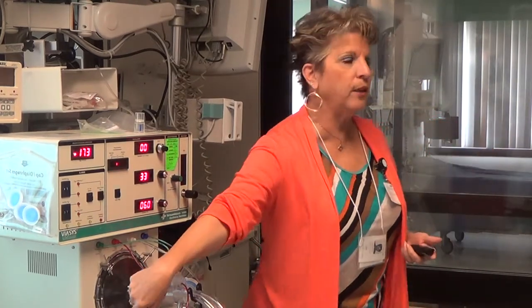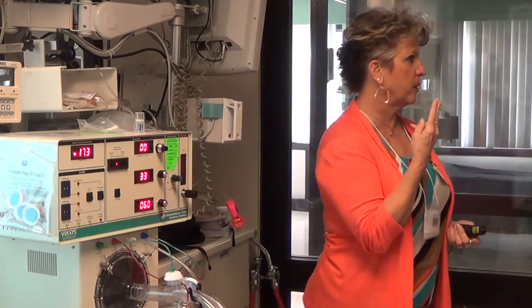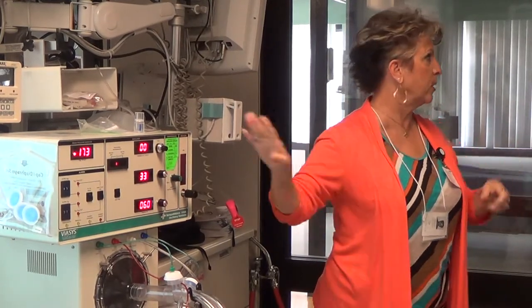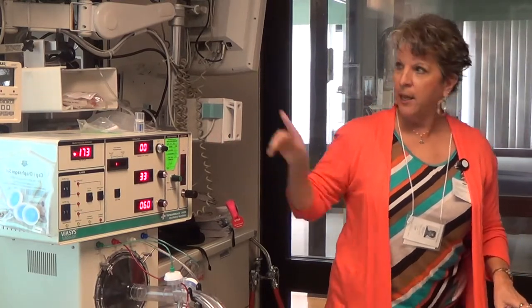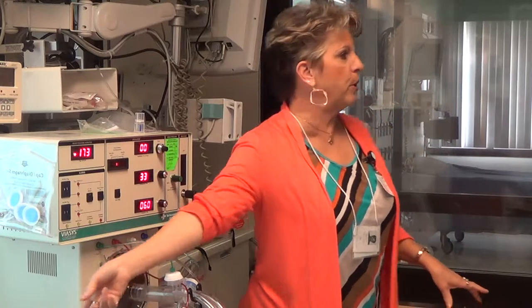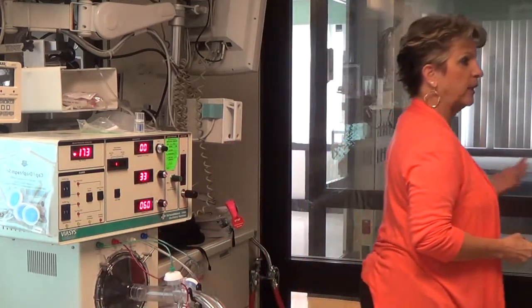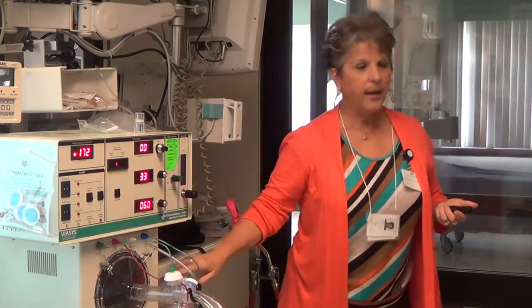You guys know that your blender is teed in to the compressed air hose. You have two compressed air hoses. Back in the day before we had blenders, you used to have to plug in two compressed air hoses because of the fan, okay? We'll talk about alarms in a minute. You guys are already ahead of the game. You know to analyze your FiO2 there. That flow meter only needs to go on 1 to 2 liters is all you need. It's the same FiO2 there as it is here, as it is here.